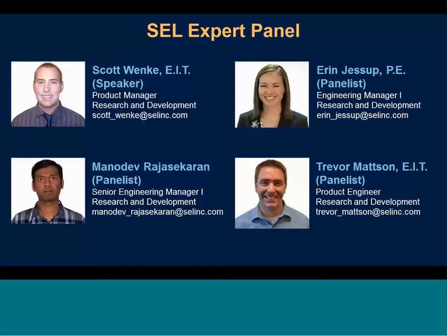There's also a couple of questions along the same line about the added delay due to these technologies and the impact to tripping time. In both sampled values and TiDL technology, yes, there is an additional delay. In TiDL technology, it's fixed at 1.5 millisecond communication channel delay. In sampled values technology, there are other varying factors, especially when using different vendors' merging units along with SEL relays, so it's a programmable thing based on your network design. The minimum is 1.5 milliseconds, but it could go up to 3 milliseconds depending on how many devices are connected and how the network has been designed.